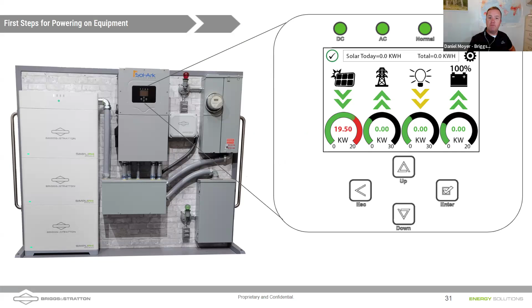After you do all the wiring, keep in mind, looking at the bottom right-hand corner, there's a box called BMS lithium bat. By default, that's not checked. So do all your wiring, don't turn the battery on, but turn the inverter on using grid, get into the settings, and check BMS lithium bat. Also, as we talk through programming, you hit the button, then also hit OK. The OK is like the save button on a Sol-Ark. So we can go ahead and do that.